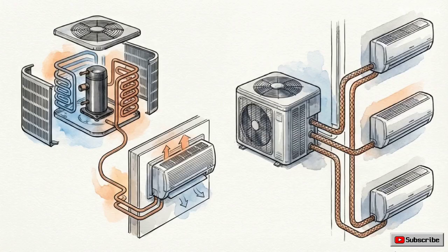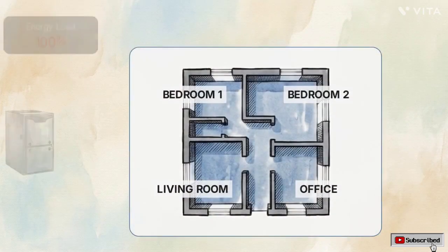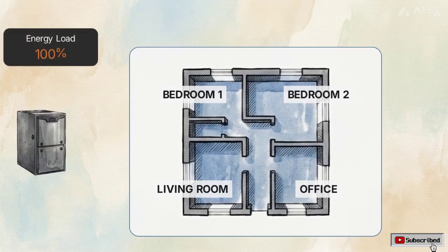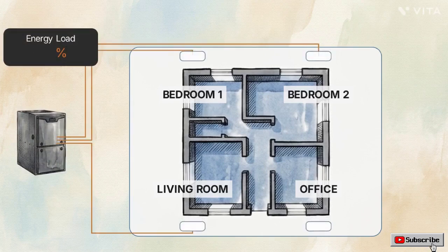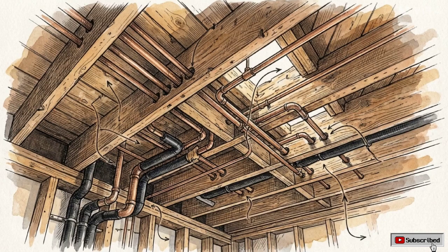physics. Beyond the compressor, you have an architectural choice: a traditional single-split system or a multi-split system. This top-down floor plan illustrates the core benefit of a multi-split. It offers true localized zoning. Cool air flows only into occupied spaces, like the living room and office. The bedrooms remain unconditioned, and your total energy use drops. The direct trade-off to this efficiency is extreme installation friction. Routing multiple lines throughout a building requires highly rigorous labor.